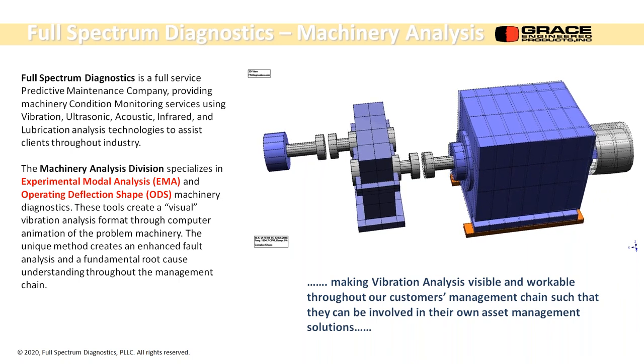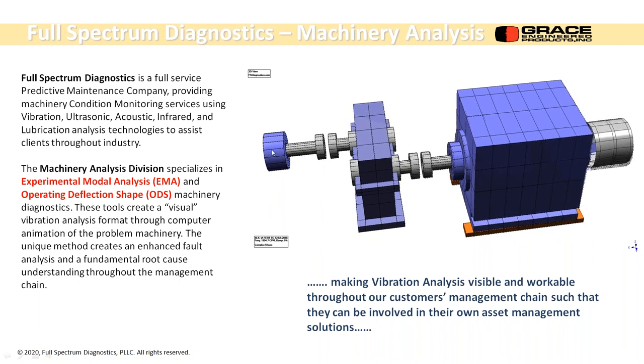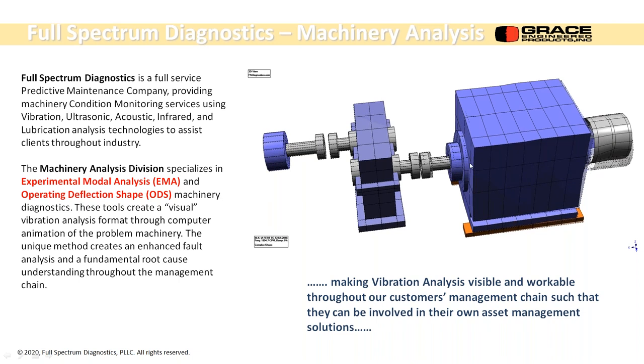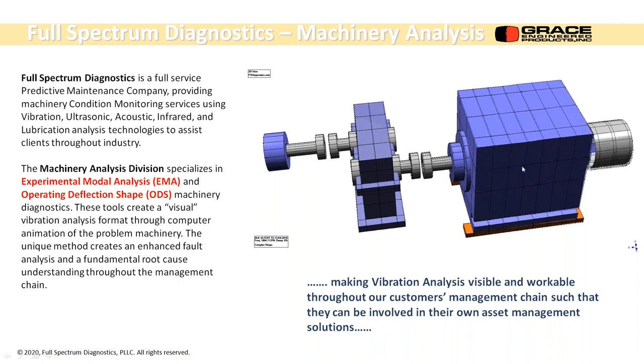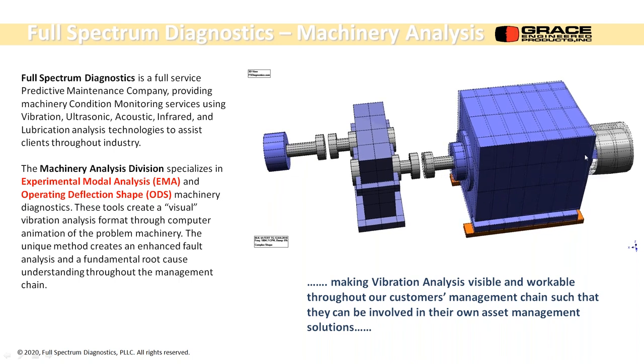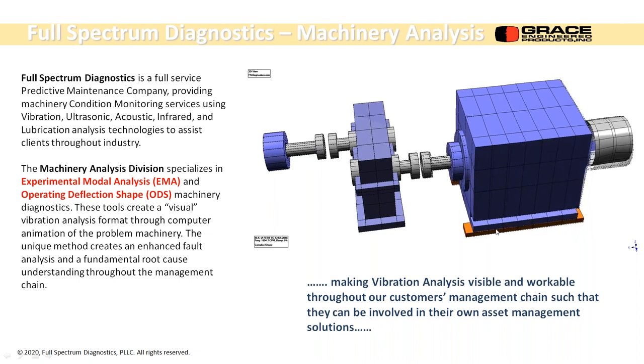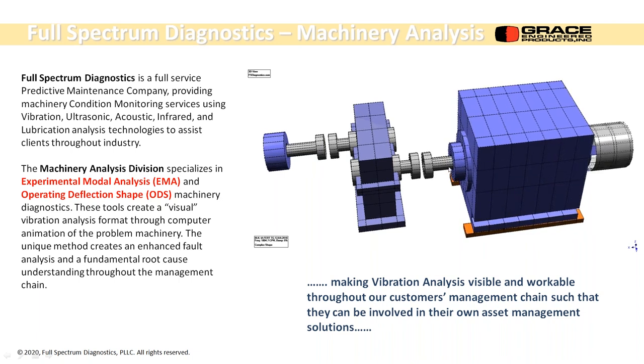And the unit you're looking at right now, on this side, there's a steam turbine. There's a gearbox with couplings on both sides, and you're coupled up to a generator. And this was one of the actual problems that we solved. There are probably 300-400 measurements here, physical measurements we had to put down. But you can see right away there's thrusting across this coupling.